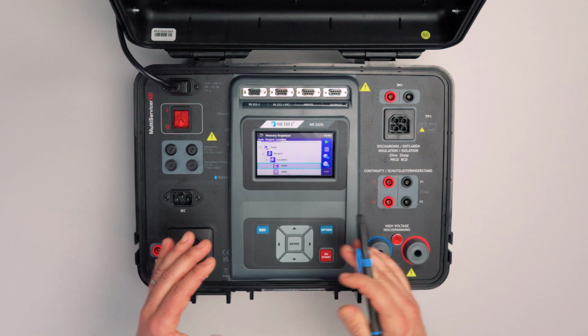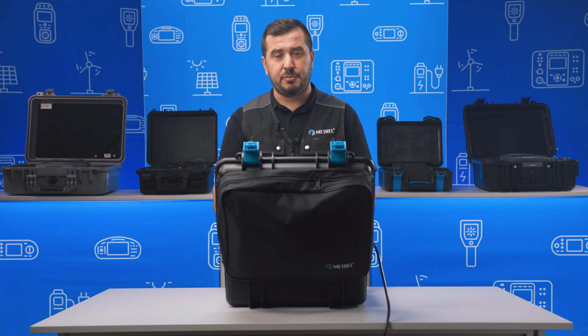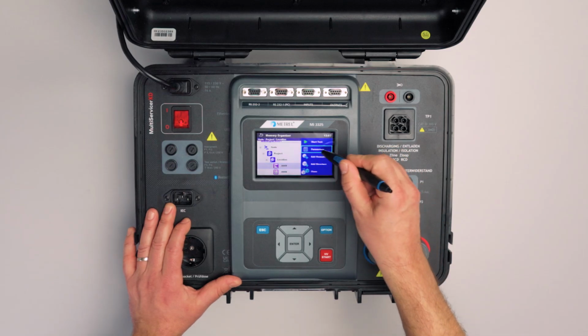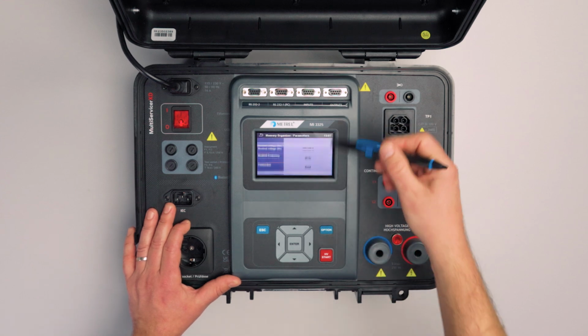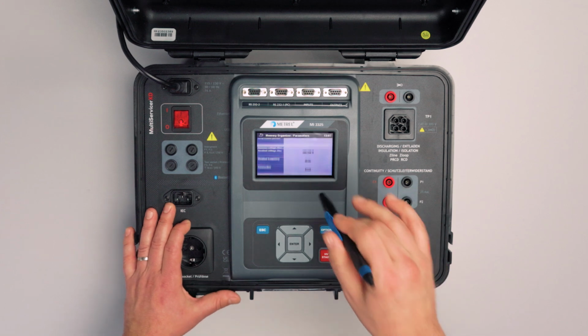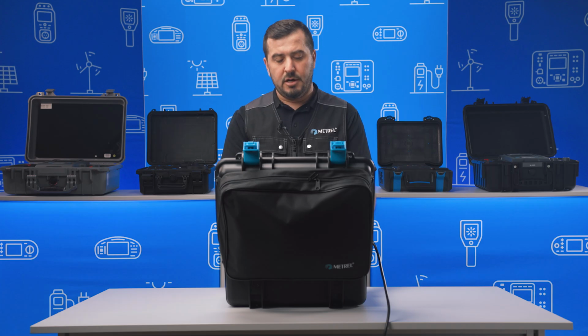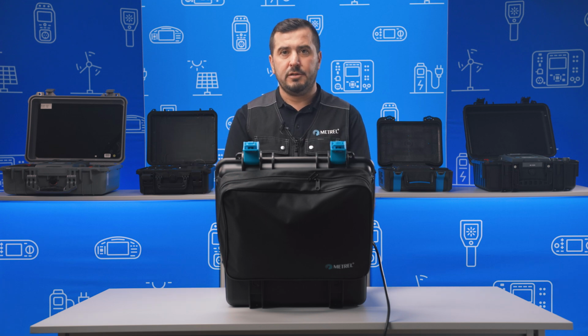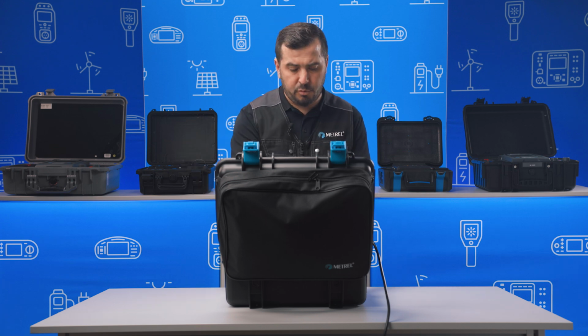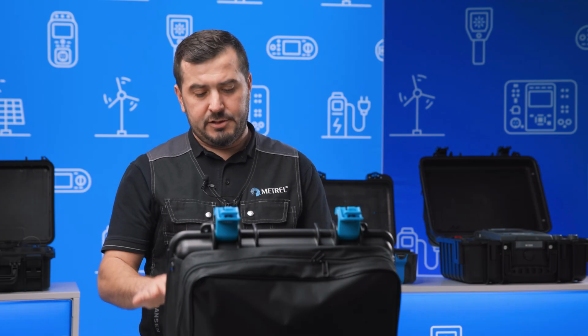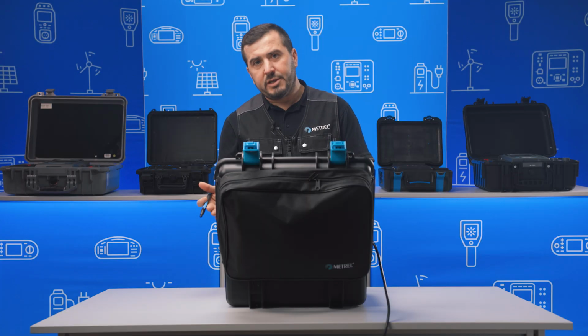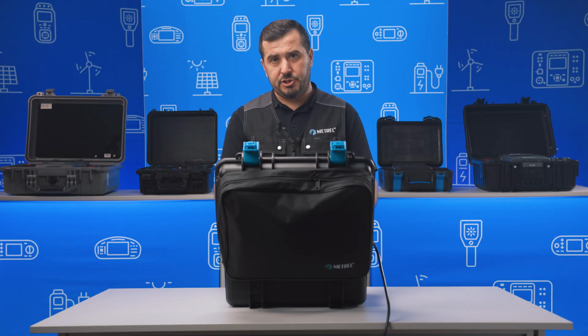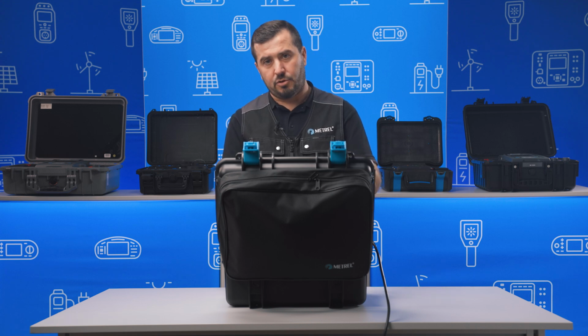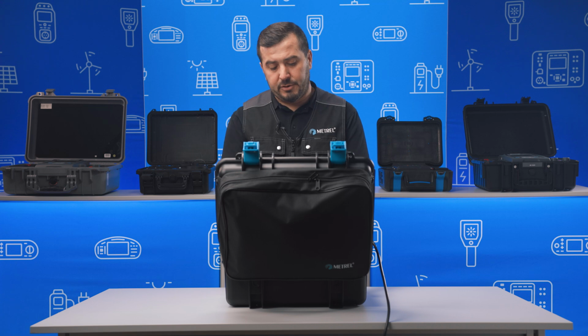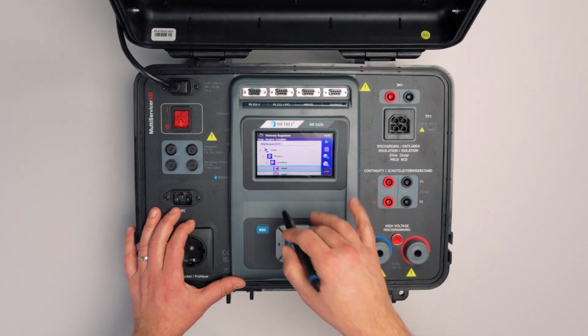Of course, for each structure element inside this memory organizer, different parameters can be added. Editing of the parameters is enabled by this option here, and all of these parameters found under the specific structure element are then also transferred to the PC software and eventually to the professional test reports. A very nice feature of this equipment is also two ways of testing, let's say. One way is to start the measurements from the single tests or auto sequences, and the other way of testing the equipment is to start from the memory organizer.